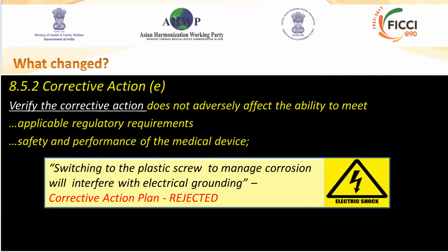Corrective actions also need to verify that the corrective action does not adversely affect the ability to meet applicable regulatory requirements, and safety and performance requirements. So, for example, I'm switching to a plastic screw to manage corrosion. Will it interfere with electrical grounding? All of those types of things need to be looked at carefully to make sure that they don't create a new hazard.